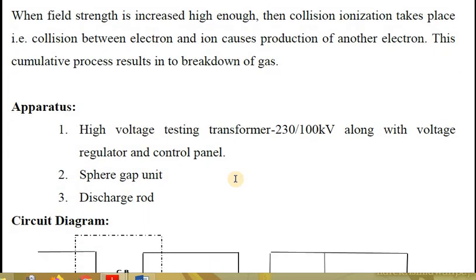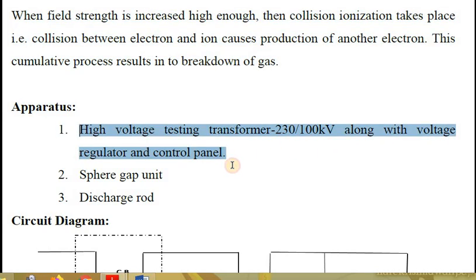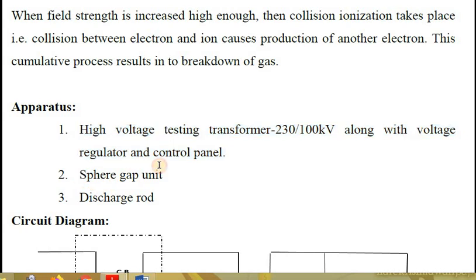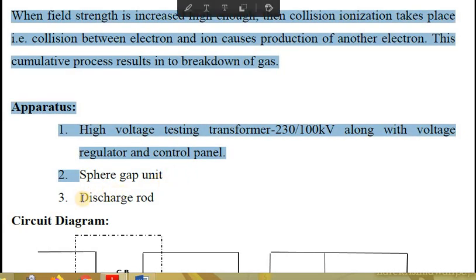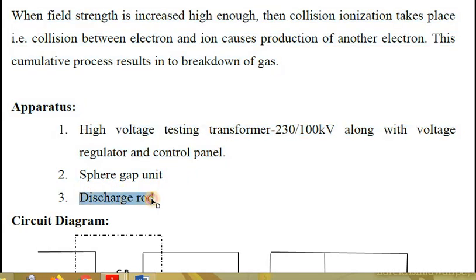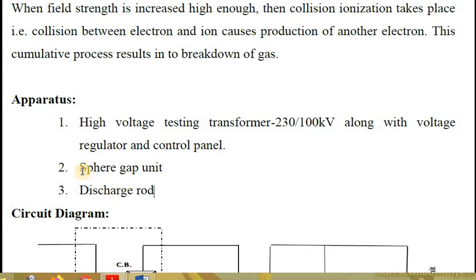For this experiment, we need some apparatus. The apparatus includes the high voltage testing transformer with a range of 230 volt to 100 kilovolt, along with the voltage regulator and control panel. We need the sphere gap unit and the discharge rod. The function of the discharge rod is that whenever the spheres get charged to the applied voltage, we use the discharge rod to discharge them.